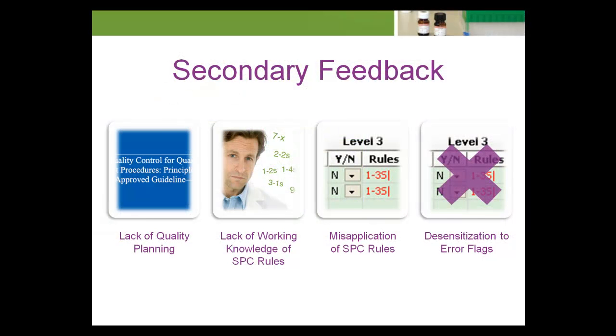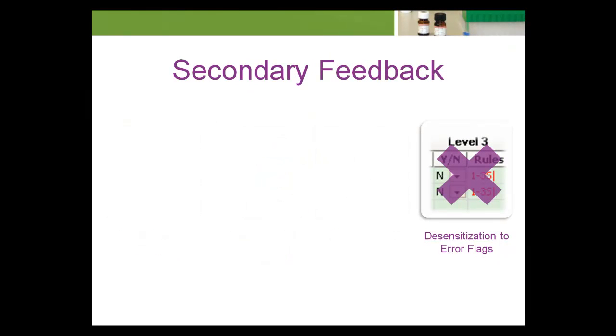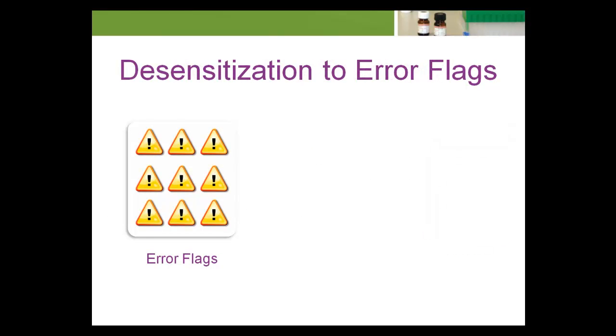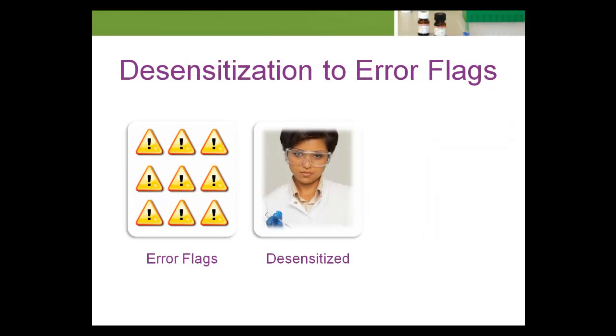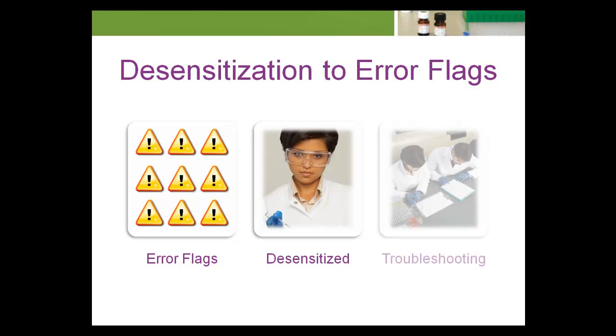Desensitization to error flags is another reason to use a secondary feedback mechanism. When error flags occur too often, bench technologists often become desensitized to the flags. Initially, they may troubleshoot every error flag, only to find that nothing is wrong. Over time, troubleshooting ceases and is replaced by the most popular and frequent response, which is to repeat the testing of the control, sometimes repeatedly, until a result falls within the limits of acceptability.